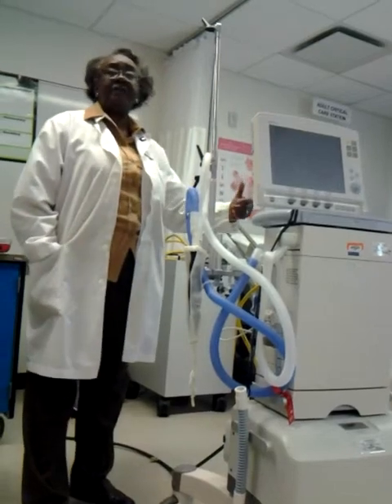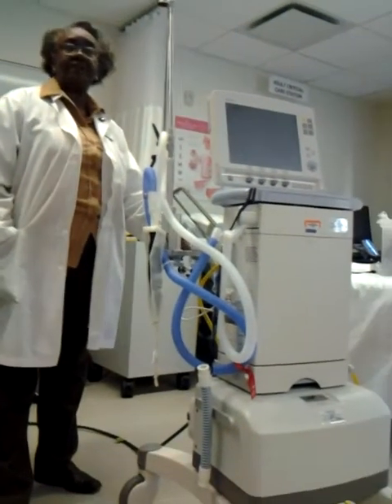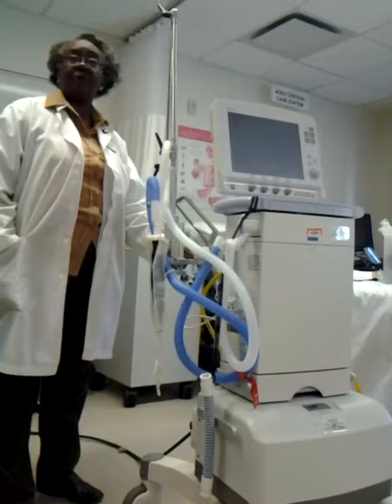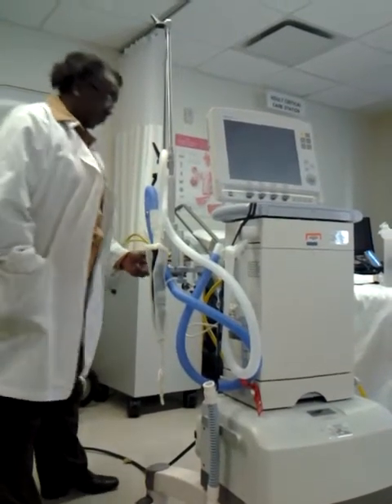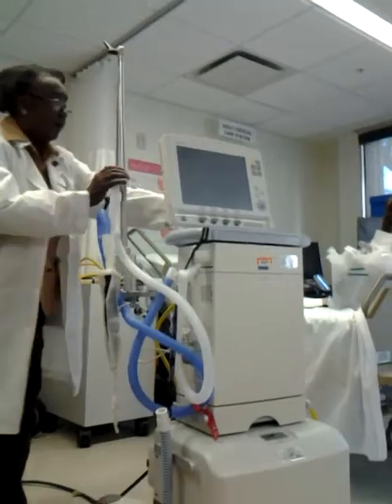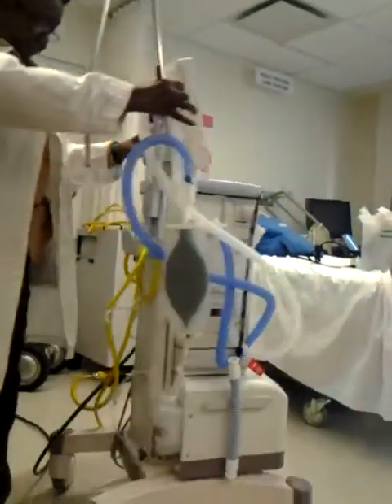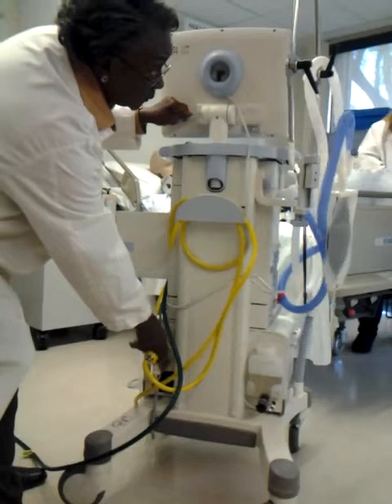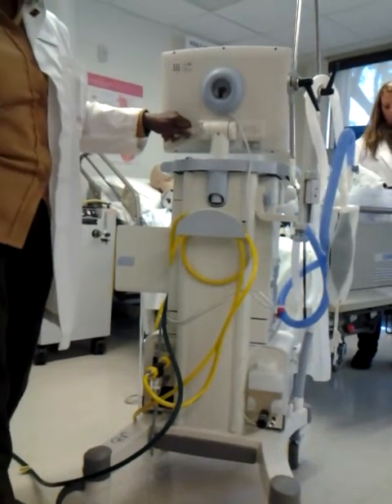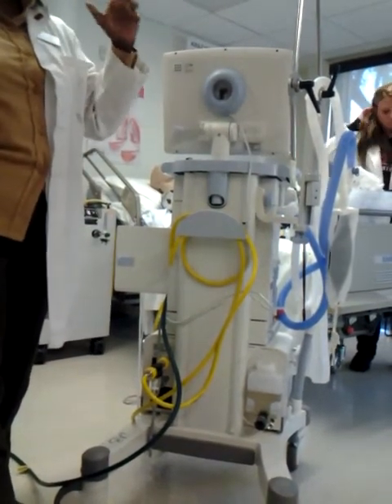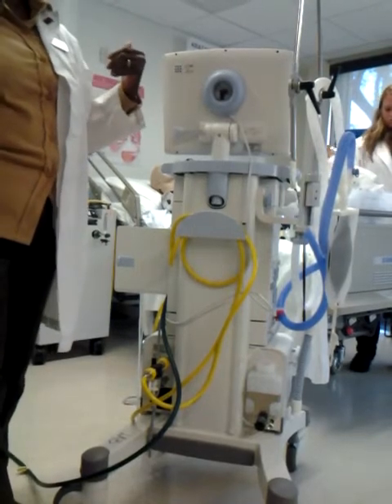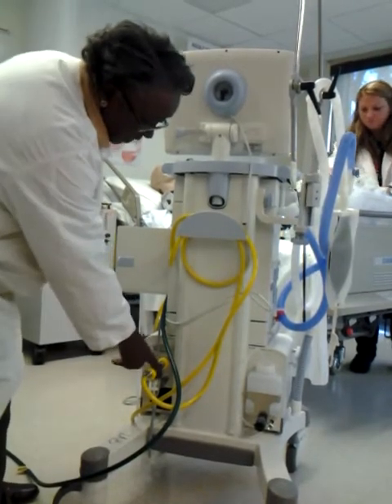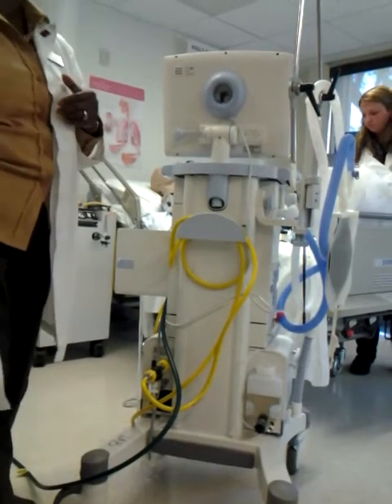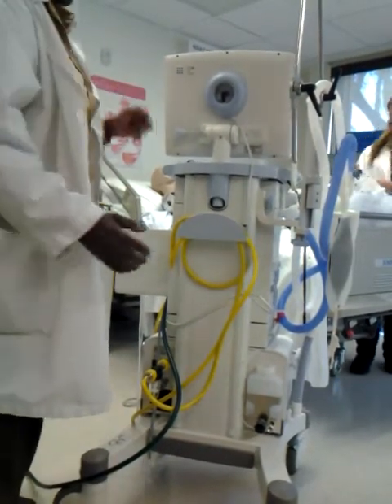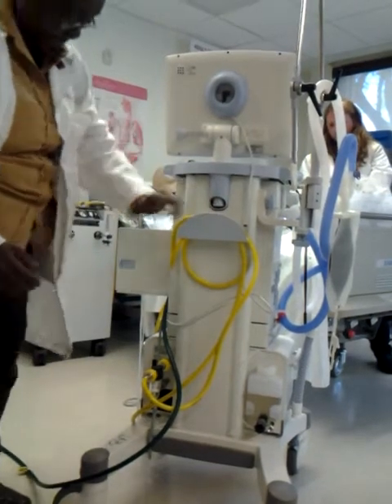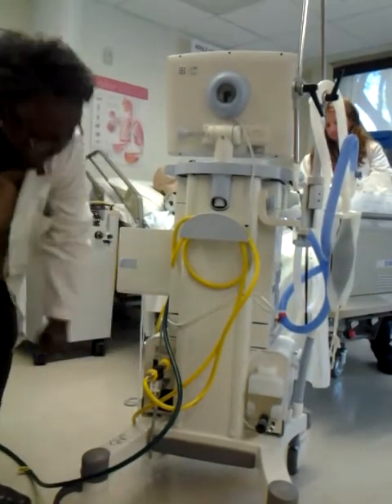That way, if you don't have piped-in air, this compressor actually has to be turned on, whereas the 840 does not. There's a little button in the back here that turns on the compressor. And there's also a little water trap down here, because it's taking in room air and then compressing it and sending it through, you may get some moisture in the system, so that will be collected down here. And you also have a little condensation bottle on the bottom there. I really don't get a lot of condensation in that. To turn on your compressor is here. This is the filter for your compressor.